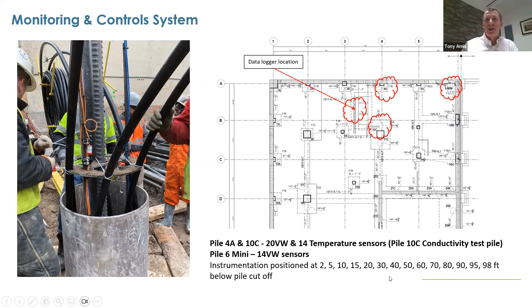And you see that we've got instrumentation spaced out through the depth of the pile, and that's all running back to an instrumentation panel next to the main manifold. One of the important things is to understand the conductivity value of the ground and resistivity, because they're key design parameters used in the geothermal design. Running a test in a foundation itself probably takes a little bit longer than a conventional borehole. In this particular case, we ran the system for probably 114 hours. So what's that? Four or five days.